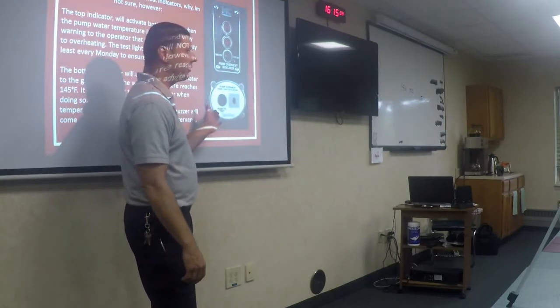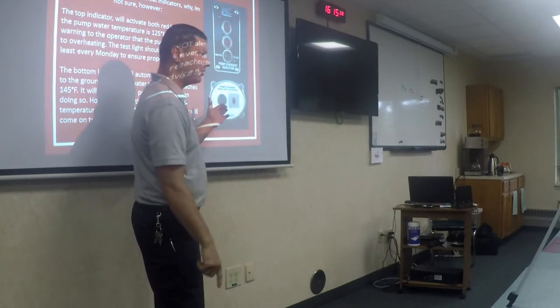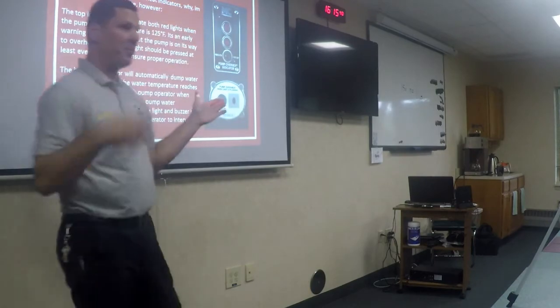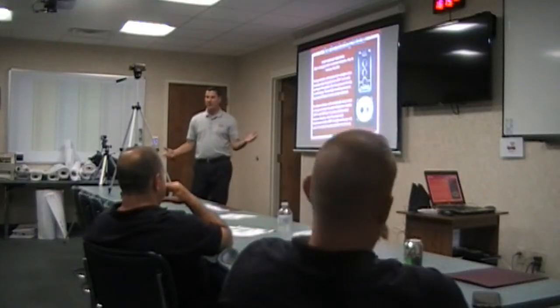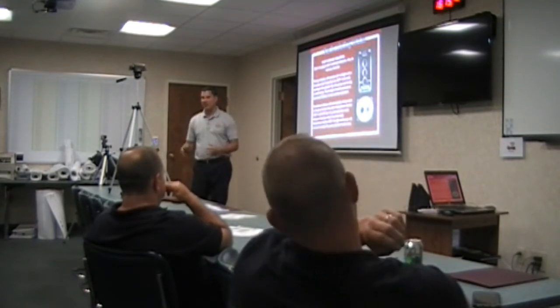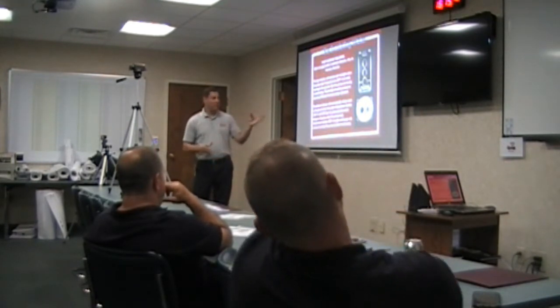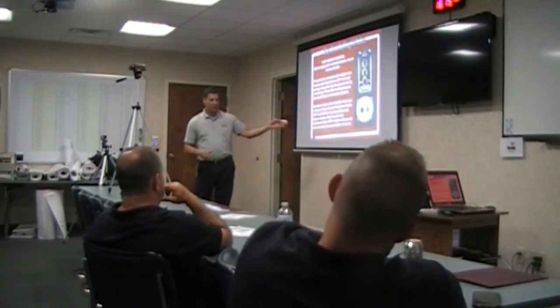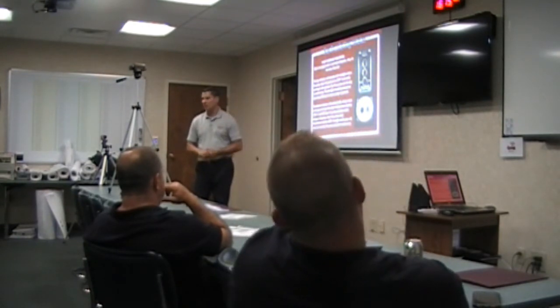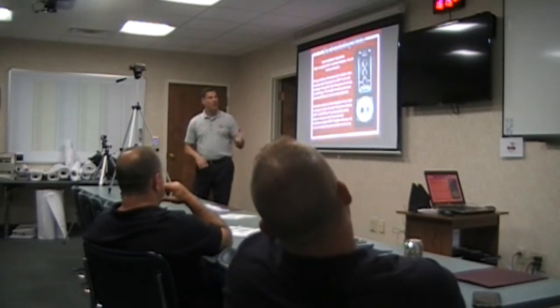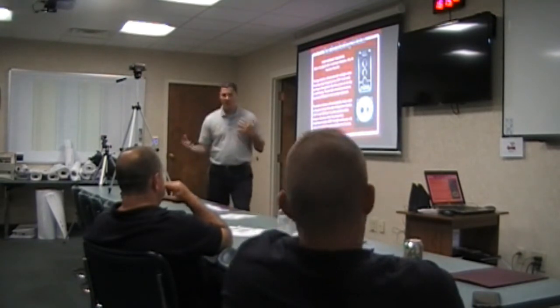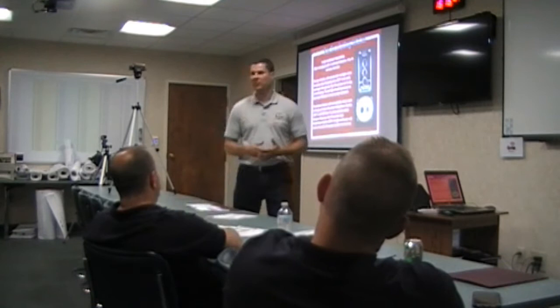I would say it's redundant, but another alarm. 145 degrees, it will automatically dump water to the ground. You won't know about it, but it'll dump water to the ground. So if you are the pump operator and water is coming out the bottom and you're not really sure why, granted there are 100 reasons for that, but it could be because of this. Go off and check, and then it'll start buzzing at 180. So that's what these two systems are doing. They're both designed to help prevent the pump from overheating.